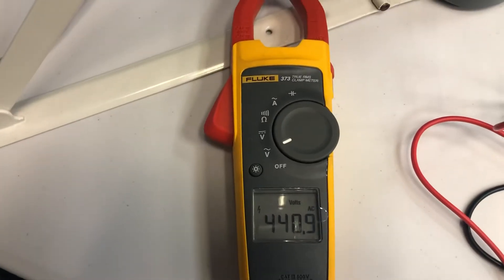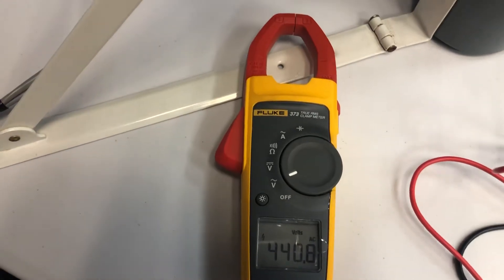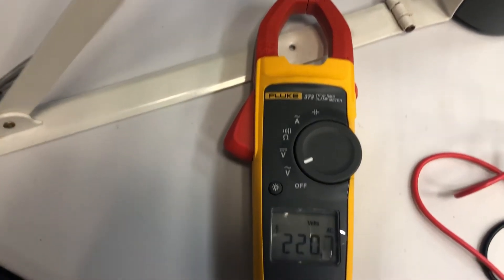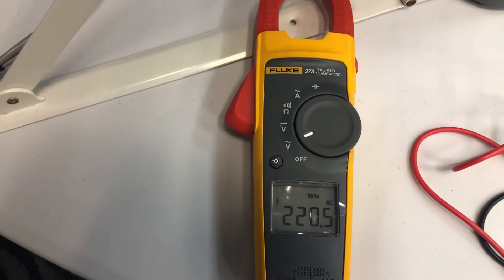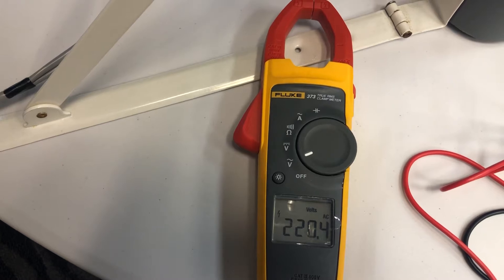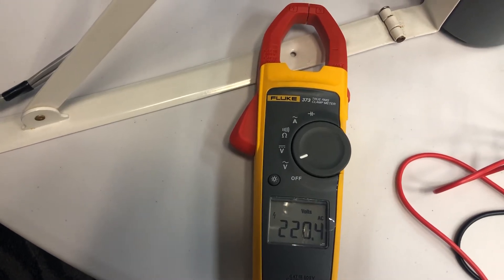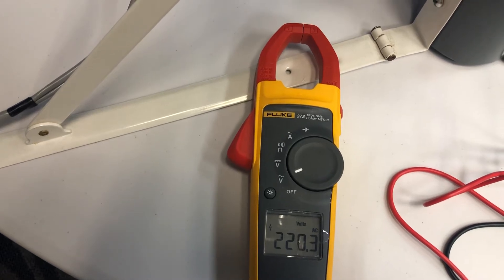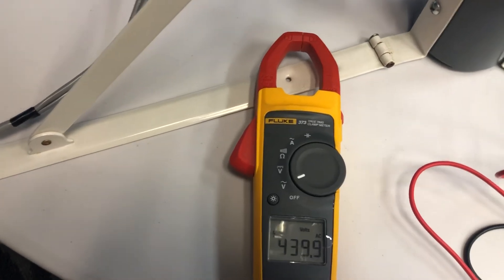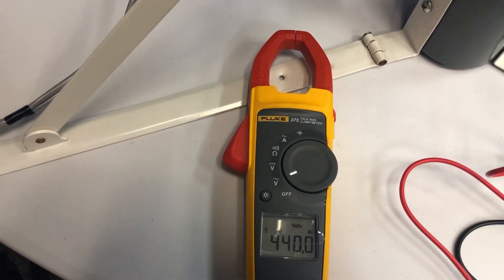Now, our machine's a little off. Phase-to-ground, let's see if I can get that out. Phase-to-ground is going to read 220, my alternators are, pulley size is just a little bit off, it needs to be up just a little bit, turn the alternator a little bit faster. But there we would have 240, so if you take that 20 volts that were short, 20 volts from the other one that was short, add that to that 440, that would be 480.